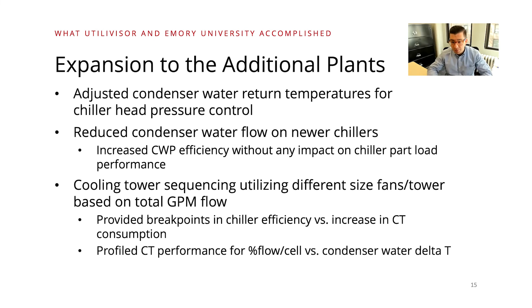So one of the things that we see, again, Emory has an enormous amount of machines of various sizes, where good practice is to constantly cycle the machines just so they're not sitting there for a long time. But looking at that data over the course of several months, they had an enormous amount of chiller combinations that at that same load, without any difference to what was being sent out to the loop, were consuming a lot in the plant themselves. So this was just to show the different variations, where you had 4 different combinations with 2 machines, 2 combinations with 3, and then 1 with 4.